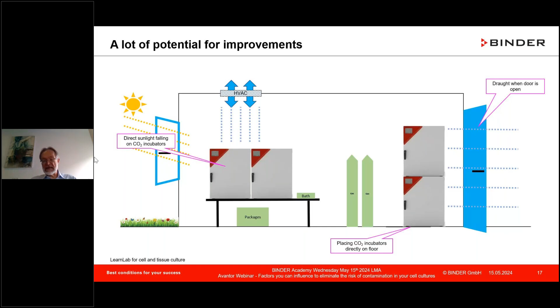Placing CO2 incubators directly on the floor without any adapter plates or casters or something like that is a no-go. Because every time somebody walks by, their feet, the air movement will transport dust, carrying contamination eventually into especially the lower one. Directly stacked on top of each other is also an issue, specifically for those, and we have many, with a thermal sterilization routine. CO2 incubators too close to the door: every time you open the door, the risk of receiving contamination is higher than for a CO2 incubator stack positioned in the middle of the room.